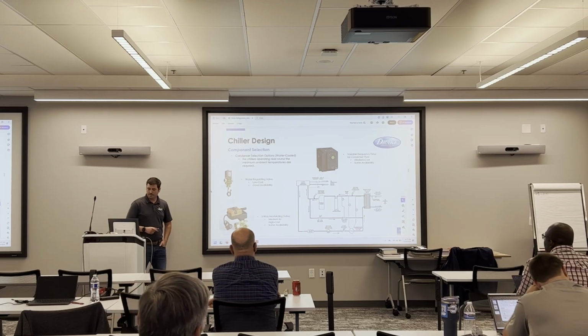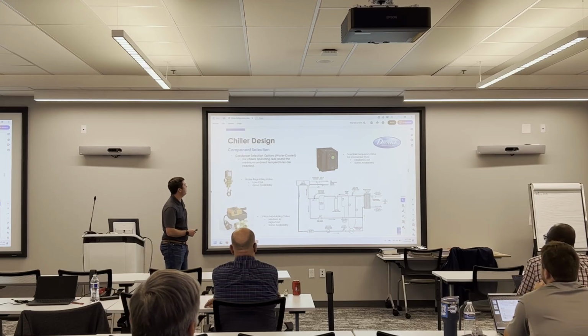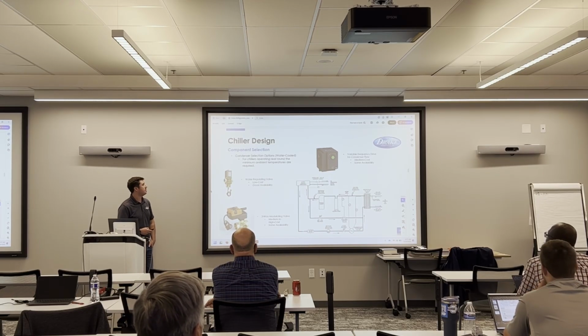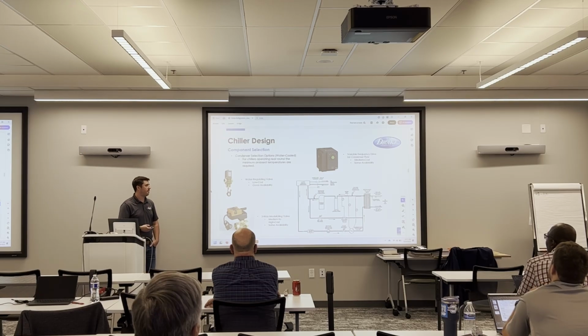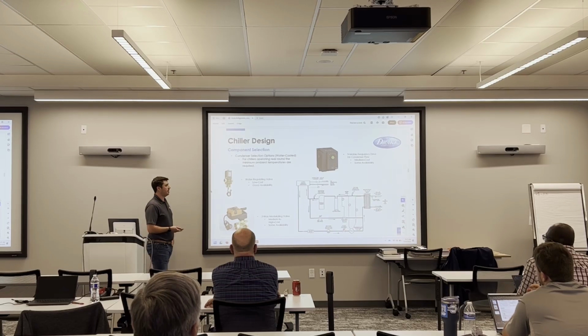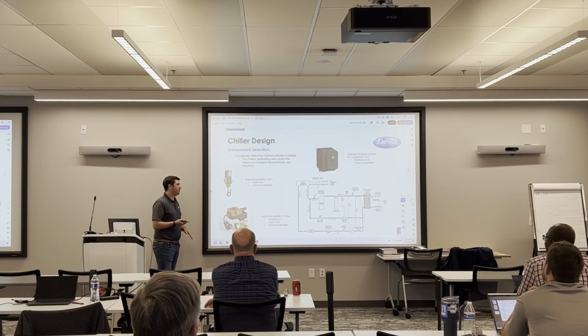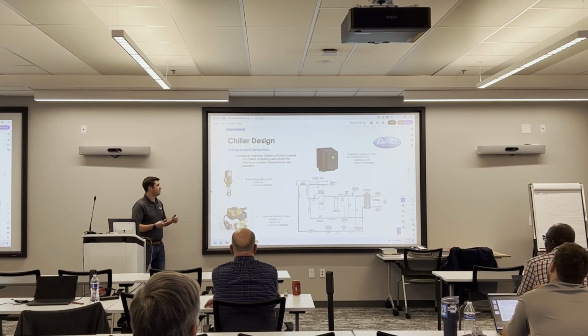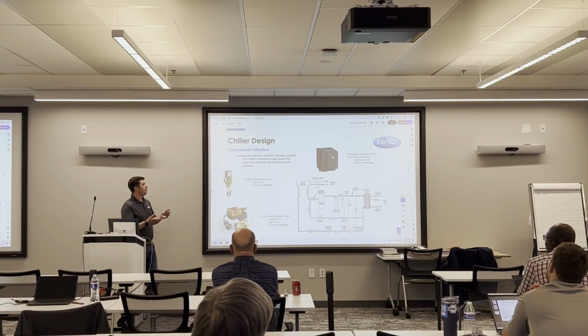And as far as some mitigation on a water cooled condensing unit, there's definitely some options that we can pursue. So for, again, chillers operating year round, your condensing water is not always going to be 70, 80, 90 degrees. So if your water starts to come into the condenser at 50 degrees, it's going to drop your discharge pressure. So there's some mitigations we need to put in place to keep our head pressure up.